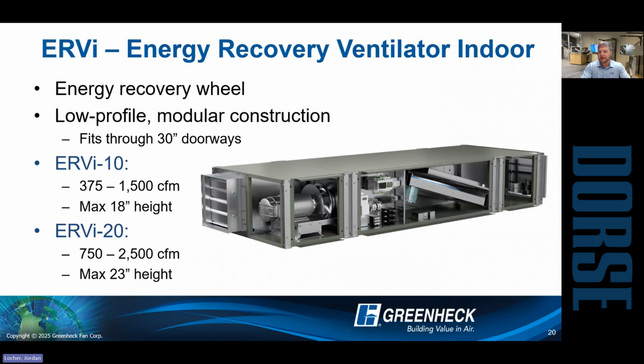So starting off with that ERVi, right, we do have two different cabinet sizes. So this is the ERVi 10, goes about 375 to 1500 CFM, and that is an 18-inch tall cabinet, right? We also did an ERVi 20, and that goes all the way up to 2500 CFM, and then that cabinet is 23 inches tall. Right, so you can see there's a lot of technology really in a small package, right? So there's a lot of controls, a lot of different things going on, EC motors, dampers. So to get all of that technology into as compact of a space as possible and still keep that modularity was something pretty innovative.